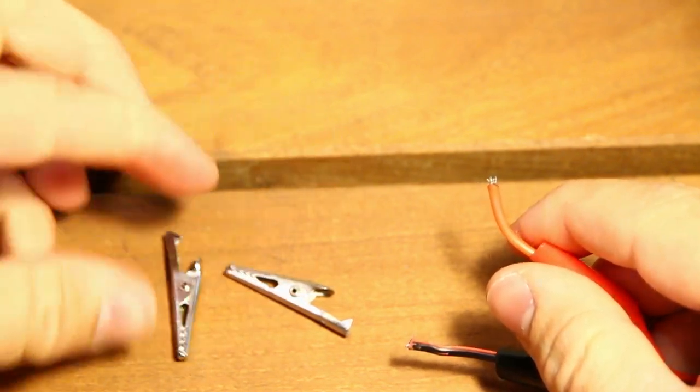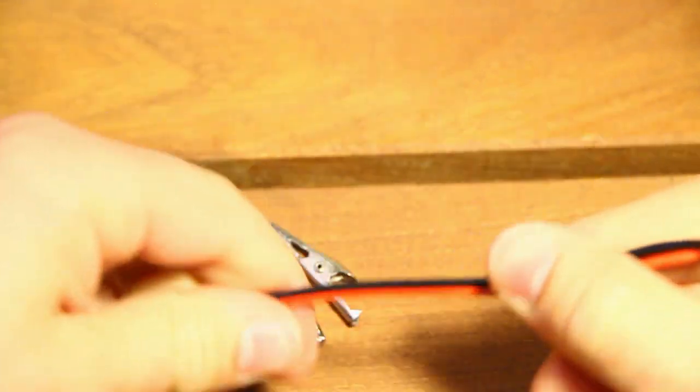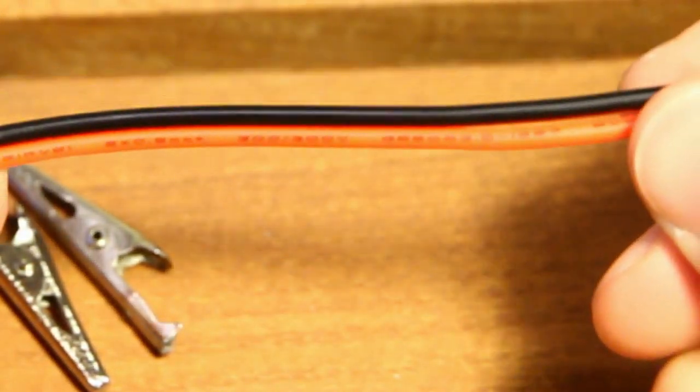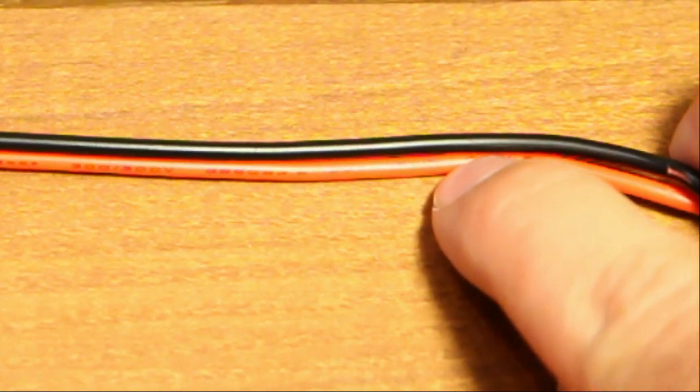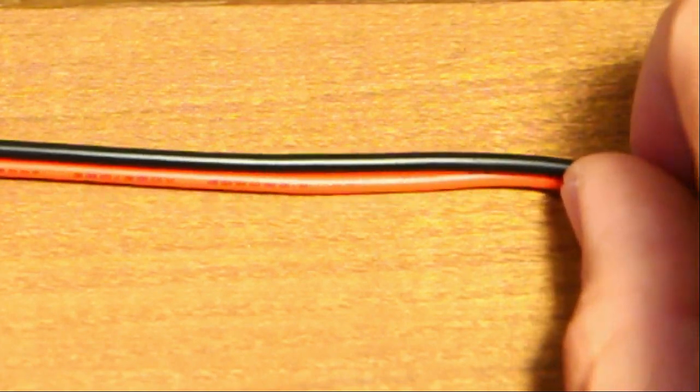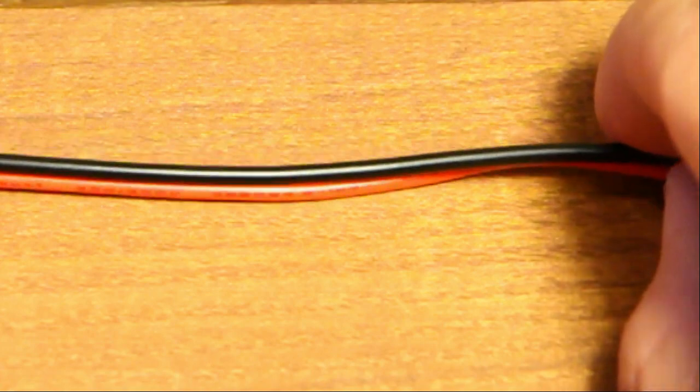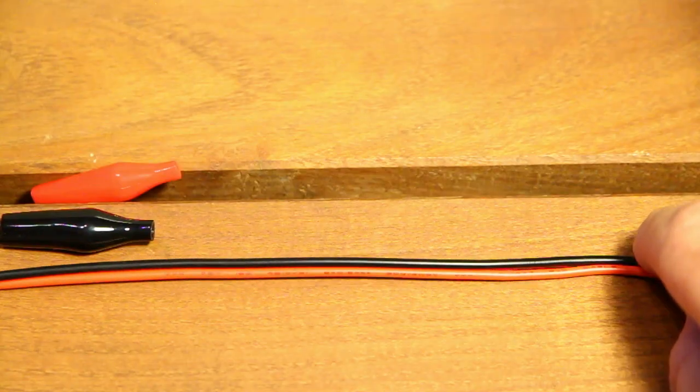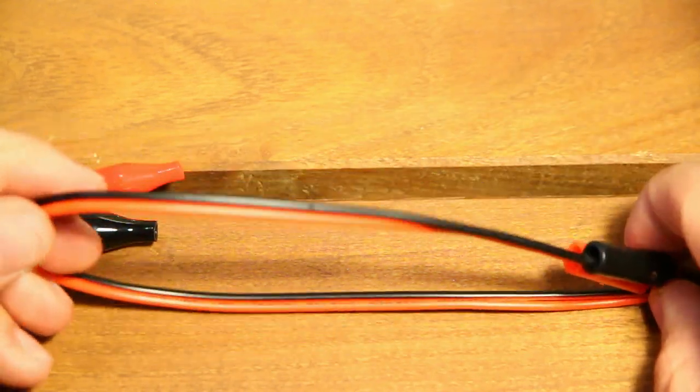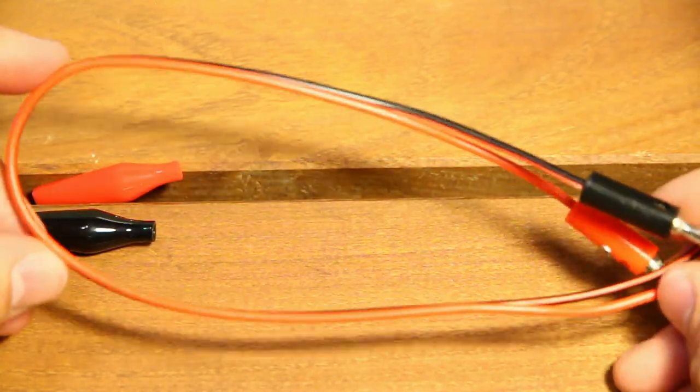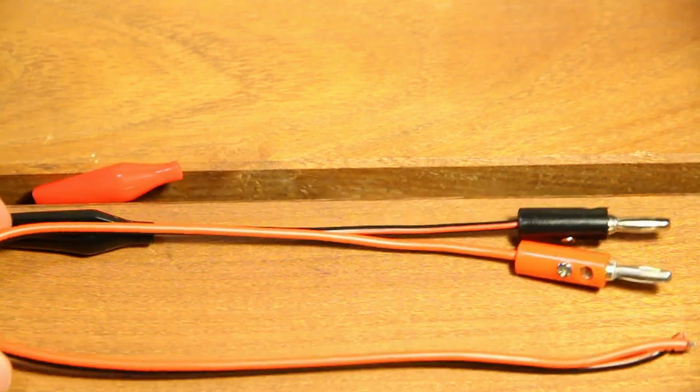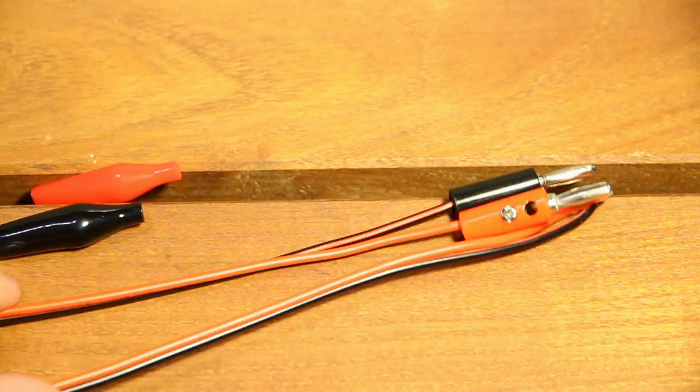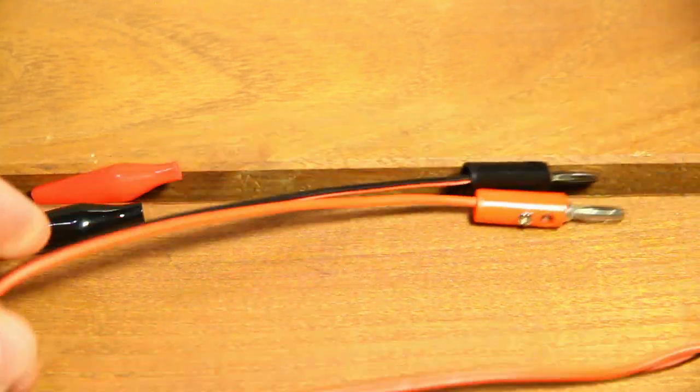This is something interesting. The wire itself actually has a marking on it. These are PVC isolated. Two times 0.5 square millimeters and up to 300 volts. So there are actually markings on this wire. That's great. But what's not so great is the cross-sectional area of 0.5 square millimeters is actually not big enough for this application because this power supply puts out up to 10 amps. And for that you would require at least one square millimeter of cross-sectional area. So exactly double that.